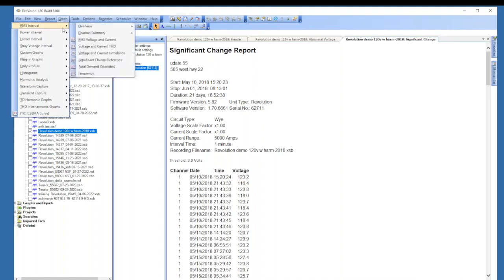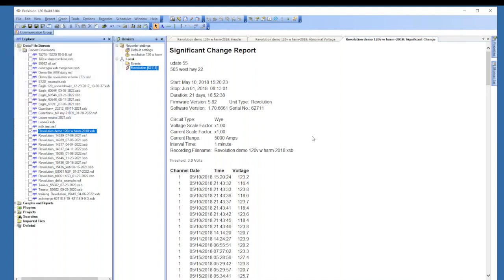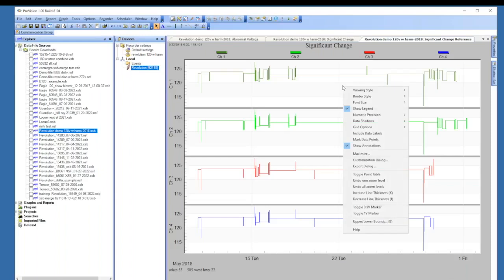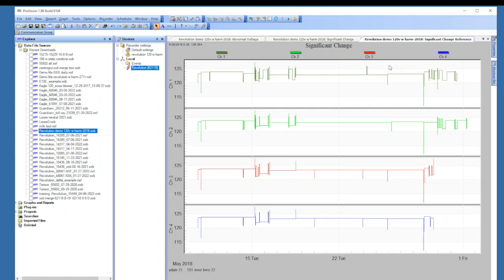So if you go into your graph tab, RMS interval, and then significant change reference, in your graphs you can always right click and you can increase and decrease the zoom and zoom in and out there. So I'm going to hit my K key and darken that up a little bit so you can see it. But you can see your voltage fluctuation. So again, if someone's complaining about flicker, or if you see a loose neutral, someone's complaining about equipment burning up, you can see pretty much in one glance the whole recording. Now there is a limit there of 1,000 events.